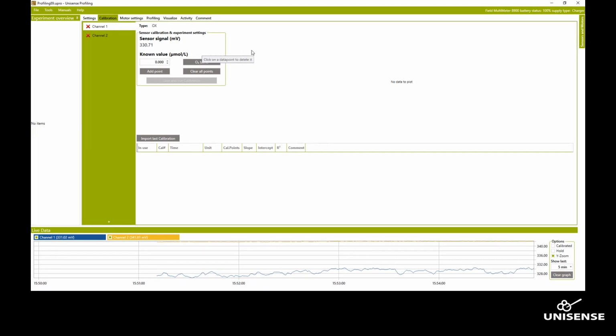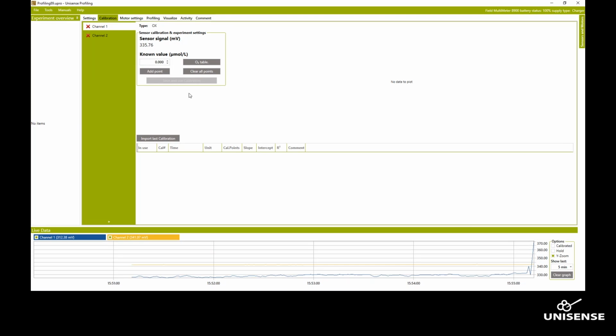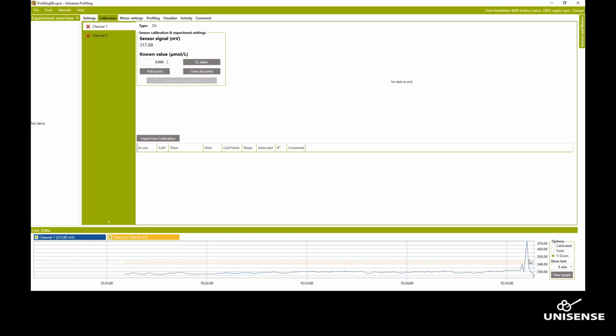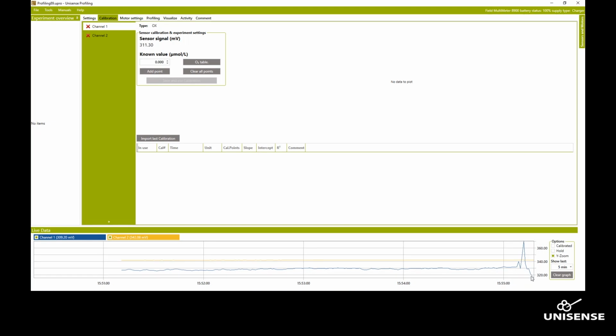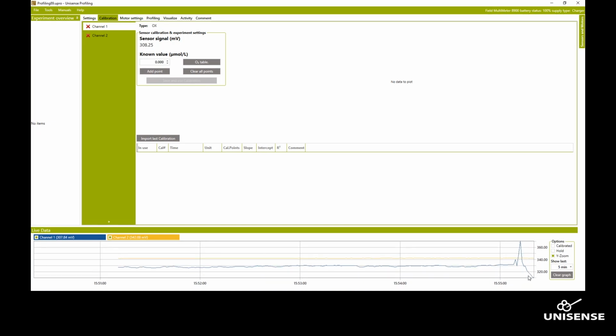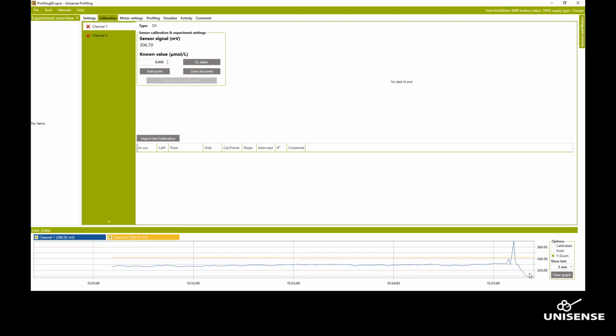As I've mentioned earlier, we need 2 points for the calibration. One would be a 0 and one would be a known concentration. I'll start with the known concentration. So now I will put the sensor into the calibration chamber. And you see when I touch the sensor, it always gives a bit of noise, and now it's in the calibration chamber. The temperature there is about 22 degrees and now has to stabilize.